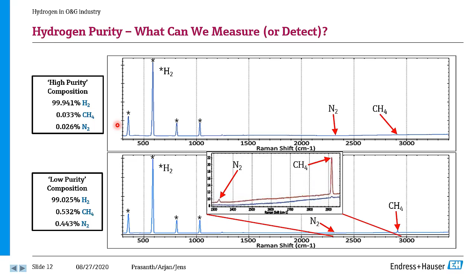What I'm trying to show in this slide in terms of the hydrogen purity is basically, out of an SMR, you can have a high purity composition and a low purity composition. What I mean by high and low, you can refer that to the percentage of hydrogen. What we have here is 99.941% hydrogen, and on the low purity composition, it is 99.025. What you see on the spectrum here is a spectrum out of our Raman analyzer. I will come into detail of that in the coming slides.